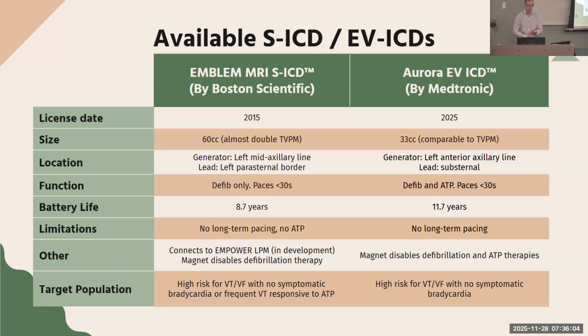The Aurora by Medtronic was just released. Its main advantage is that the lead is substernal rather than parasternal. So by placing the lead closer to the heart, it's able to use a smaller amount of energy to shock. And so because of that, the generator's half the size. The battery doesn't have to be as big. And the battery actually lasts longer, 11.7 years. The other advantage is that it has anti-tachycardia pacing. So you can avoid having to shock the patient if you're able to break the tachycardia with anti-tachycardia pacing. And again, it is magnet responsive.